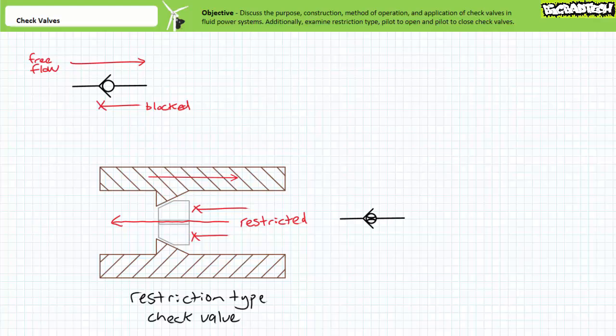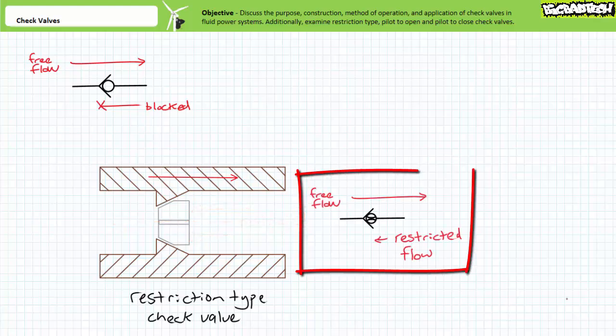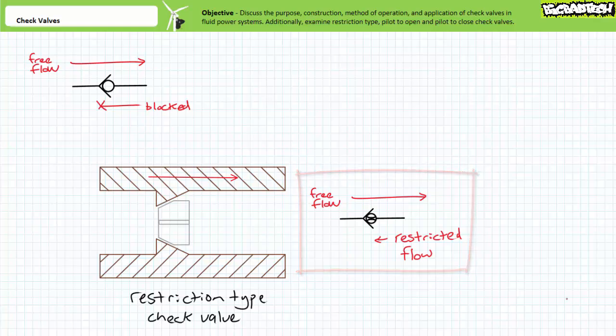Given a smaller orifice, only a smaller quantity of fluid can negotiate the narrow path in the same time. Both flow rate and actuator speed are therefore reduced when the restriction type check valve conducts metered flow in the restricted direction. The schematic symbol for a restriction type check valve shows a regular check valve with a fixed restriction drilled through the center of the ball.